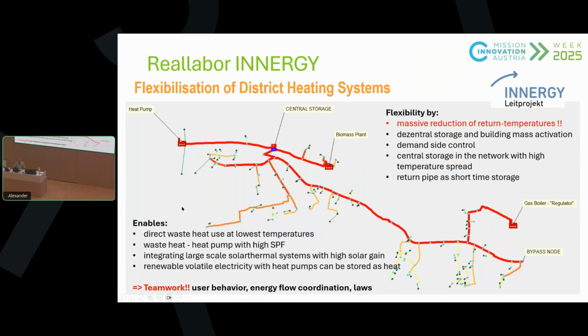And this all enables the possibility to have direct waste heat use at lowest temperatures, which means, for example, we have a steel company in the system where, of course, each degree less the return temperature of the network is, the more heat we can take out. If this is not directly possible anymore, then typically we need heat pumps to take out the waste heat and lift it to the necessary temperature level. But again, this is if we can reduce the return temperature. This also means we can reduce the flow temperature, and this is very important for heat pumps. The SPF, the efficiency of a heat pump, significantly increases for each degree less temperature it needs to produce. So lower temperature for heat pumps is an efficient electricity saving measure.